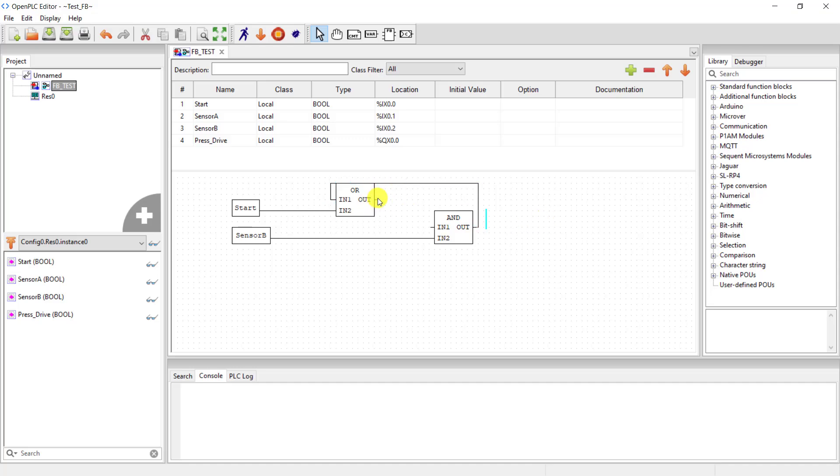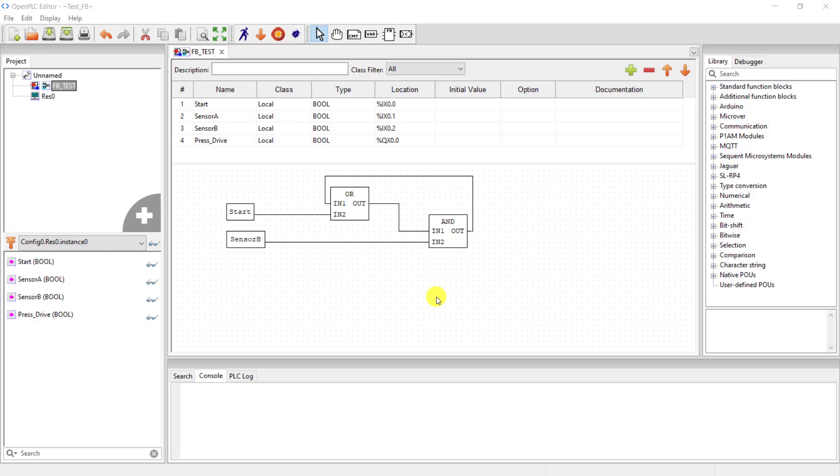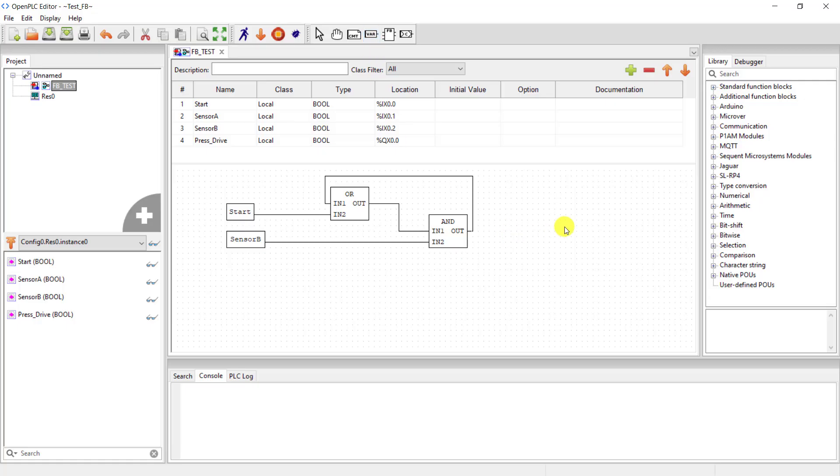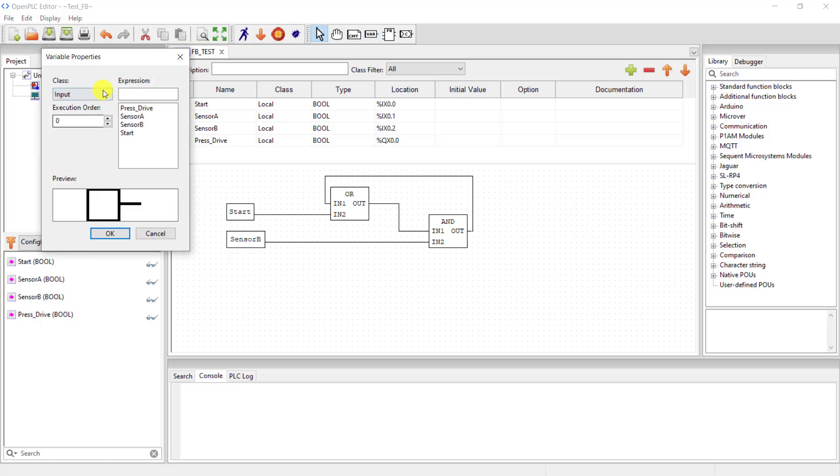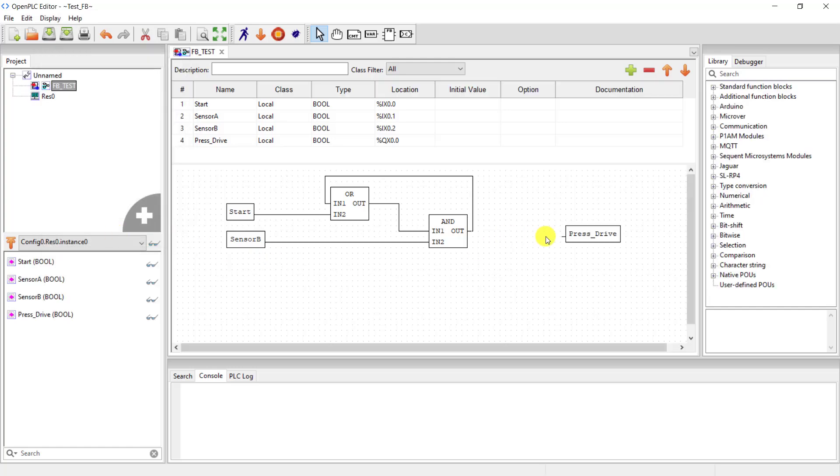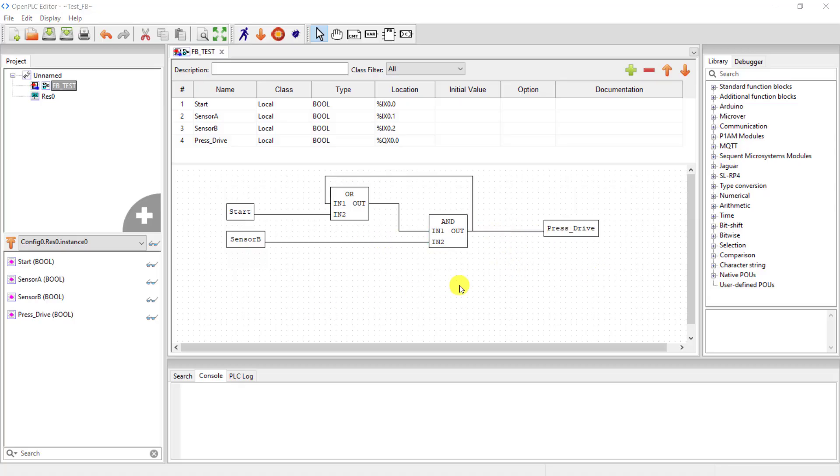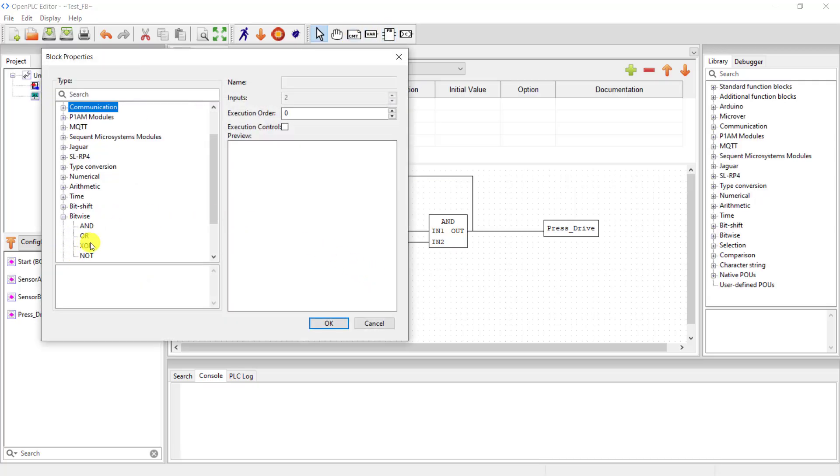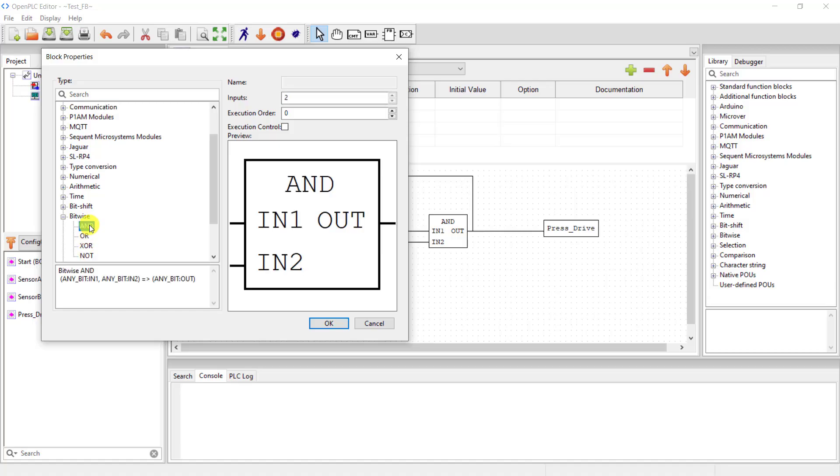Okay, and then I connect the output to the input of the last AND gate. So let's look at it quickly. When start is pressed, signal moves to the input of the AND gate, that is input 1. When the material is already detected, input 2 is also active and then we can get an output coming on. Great. And now add the output which is the press drive to it. So I connect it at the output of the AND gate.